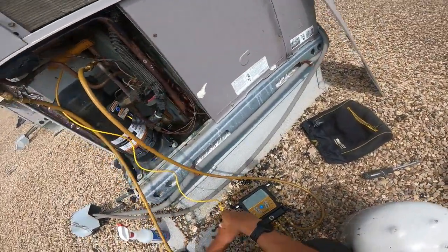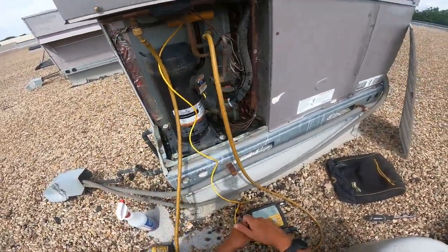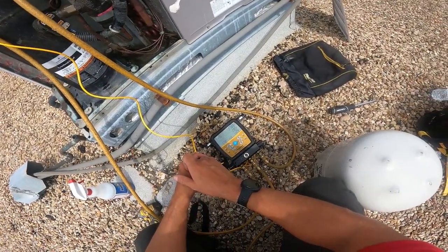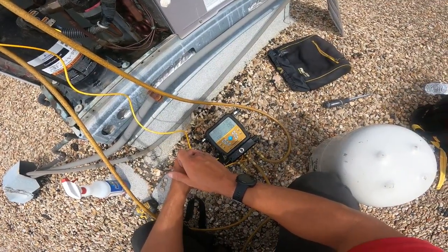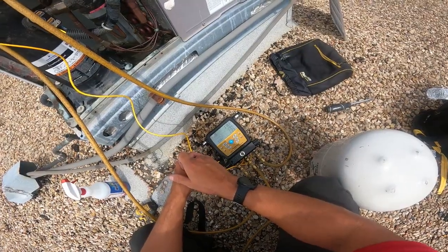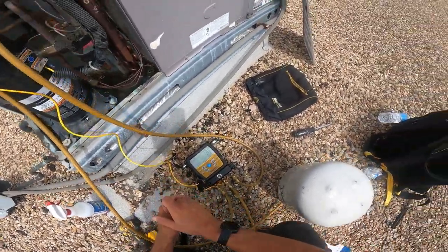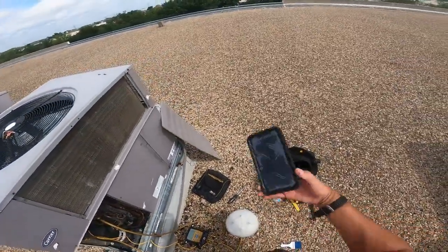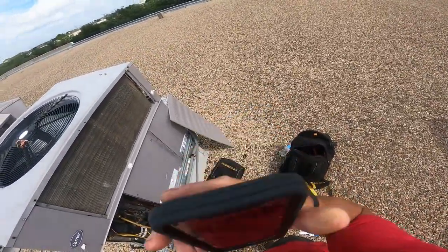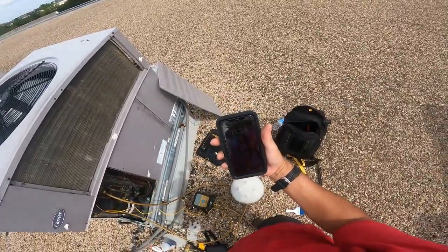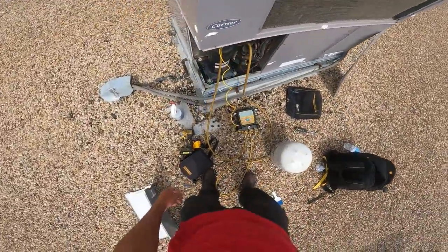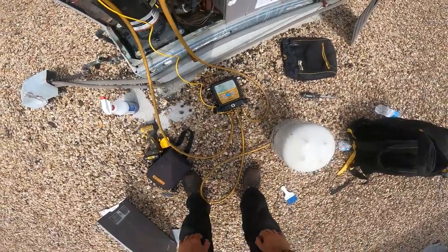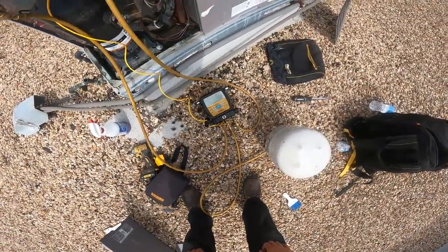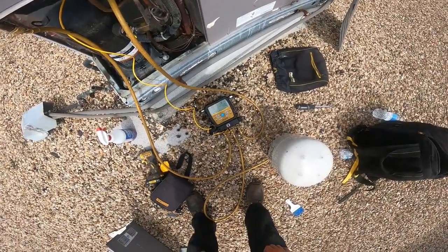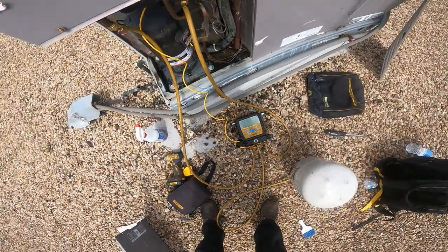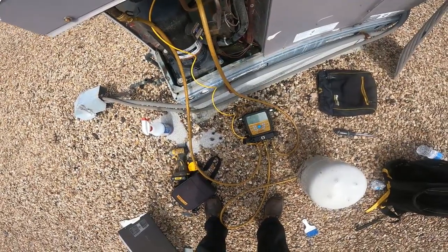It's okay, put a wet towel on it or something, make sure you got a squirt bottle with you. But yeah, that brought down my subcooling about 1 degree, and my head pressure's too high. What's the current temperature? 73. I should be about 100 degrees condensing, and I'm at 112, 113. So I'm gonna leave it. It's cooling, it's just not cooling as efficiently as they need it to.